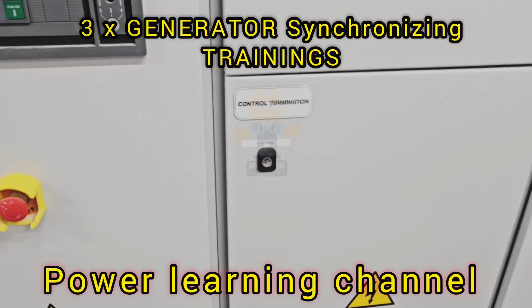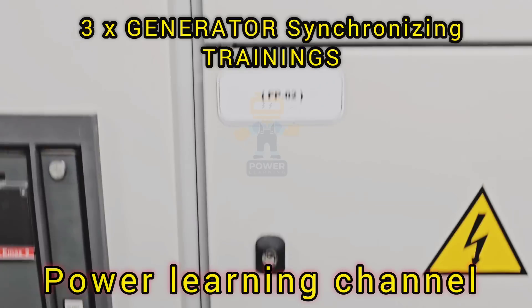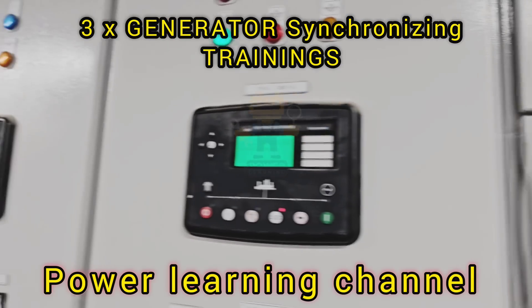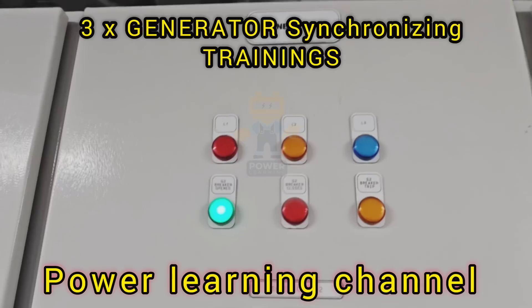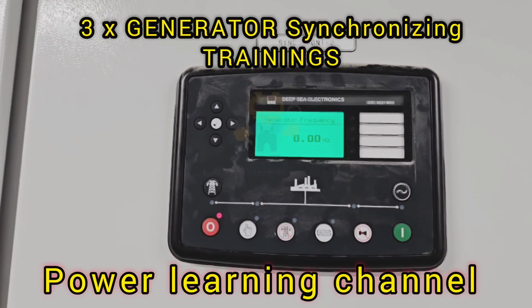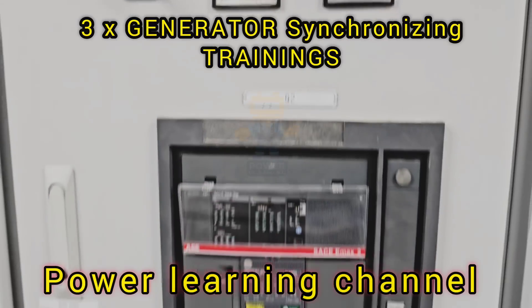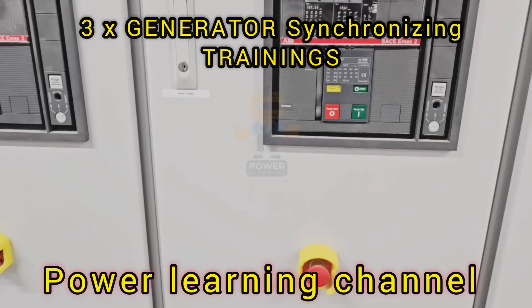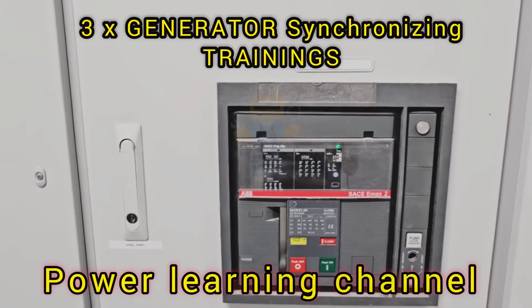Now let's talk about how the DeepSea 8610 controller comes into play. The DeepSea 8610 is a sophisticated generator control module specifically designed for synchronizing multiple generators. In our setup, we have three generators that need to synchronize and operate in parallel. Each DeepSea 8610 controller is responsible for one generator. It continuously monitors critical parameters such as voltage, frequency, and phase angle. When the controller determines that these parameters are within acceptable limits, it signals the generator is ready to connect to the system.